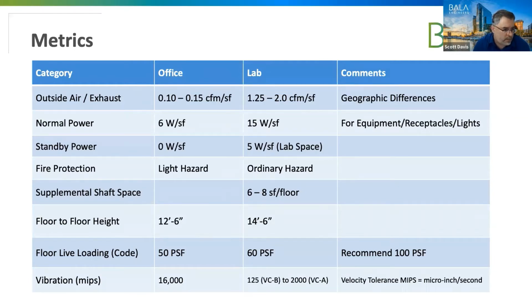Here, the next one we're looking at is the floor-to-floor heights. So a typical office, you may find about 12.5 feet floor-to-floor. With a lab, the preference is 14.5 feet, but we can make lower floor-to-floor heights work. It just means a couple different impacts, and it could be something as simple as the ceiling areas being congested, or maybe you elect to do an exposed ceiling type layout, trying to maximize the clear height.